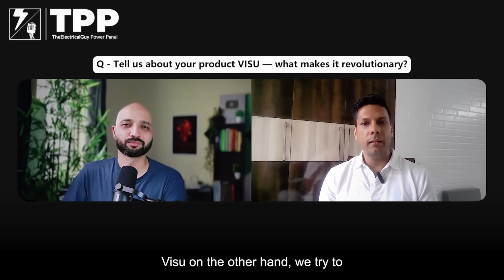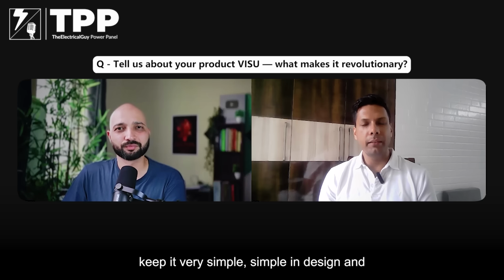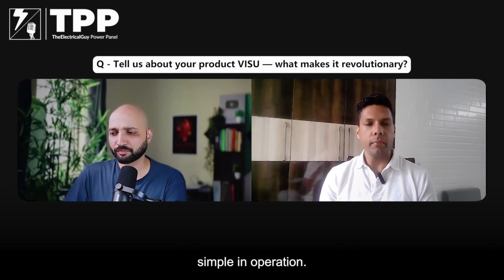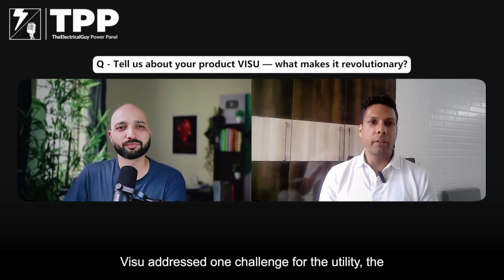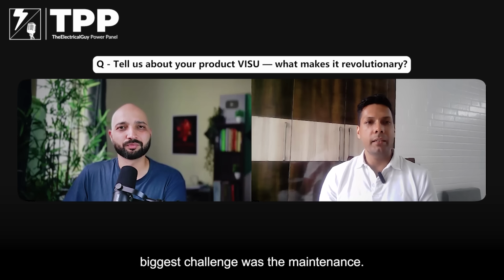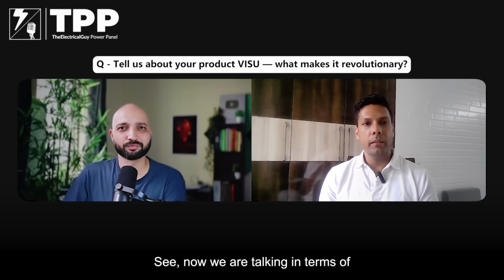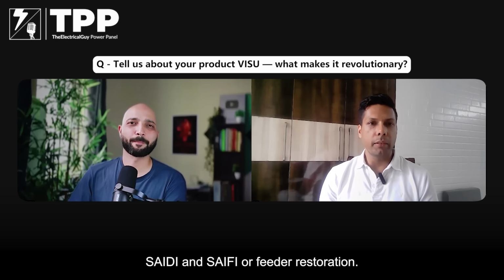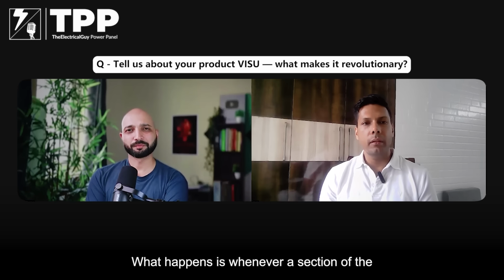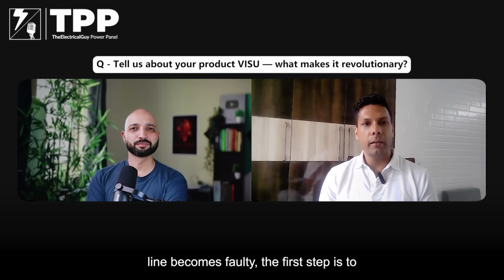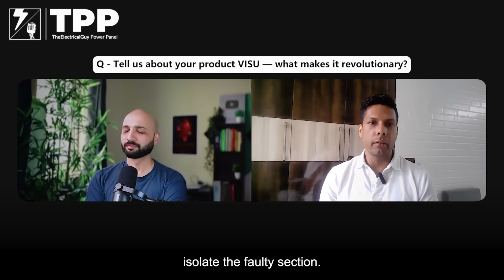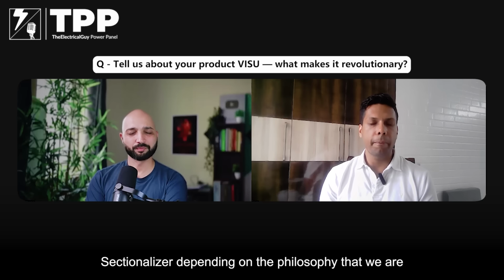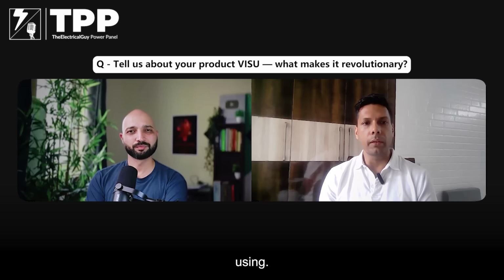VISU, on the other hand, we try to keep it very simple in design and simple in operation. VISU addressed one challenge for the utility. The biggest challenge was the maintenance. Now we are talking in terms of SAIDI and SAIFI, or feeder restoration. Whenever a section of the line becomes faulty, the first step is to isolate the faulty section. It can be done via a recloser or a sectionalizer, depending on the philosophy that we are using.